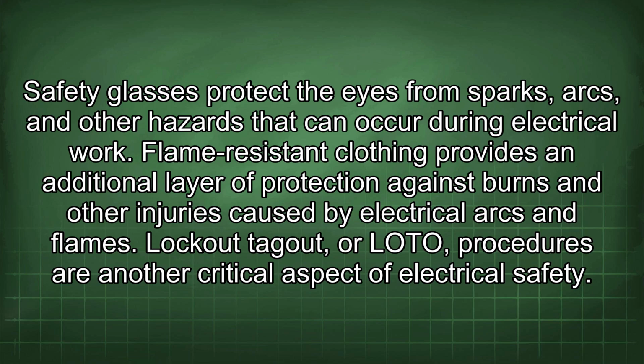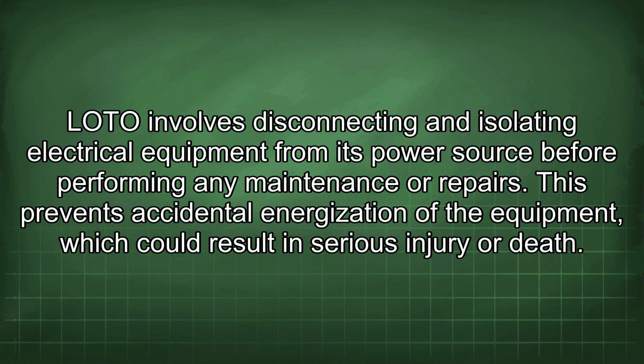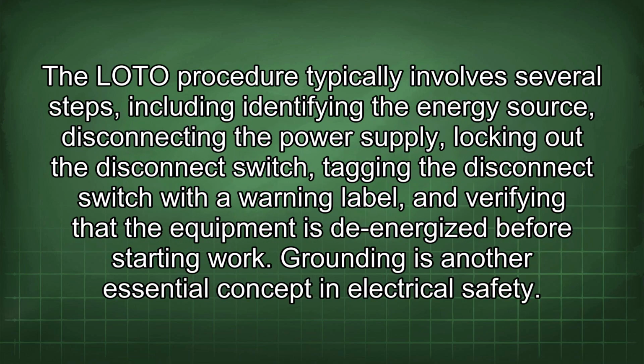Lockout-tagout, or LOTO, procedures are another critical aspect of electrical safety. LOTO involves disconnecting and isolating electrical equipment from its power source before performing any maintenance or repairs. This prevents accidental energization of the equipment, which could result in serious injury or death. The LOTO procedure typically involves several steps, including identifying the energy source, disconnecting the power supply, locking out the disconnect switch, tagging the disconnect switch with a warning label, and verifying that the equipment is de-energized before starting work.